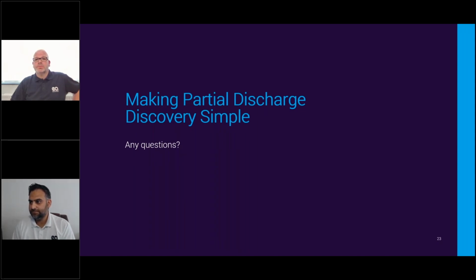Next one here. Does background noise affect the operation and results of the device? I guess this refers to the UltraTEV Plus 2. It does. There are some instances where, say, you are in a grid site, for example, and you have extra high voltage equipment outdoors. You might have overhead line infrastructure outside as well, and that can generate corona and external noise. So it can get affected by the noise.